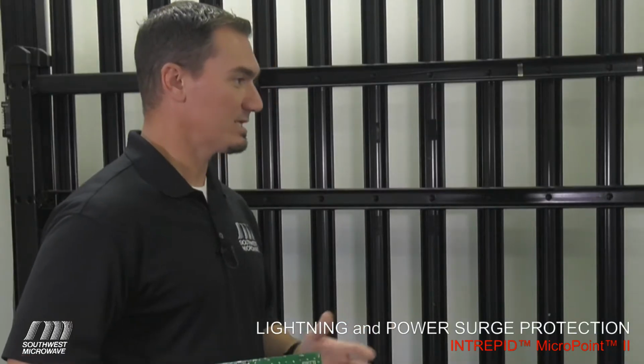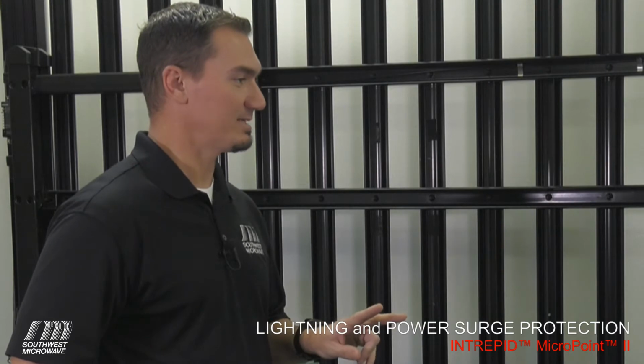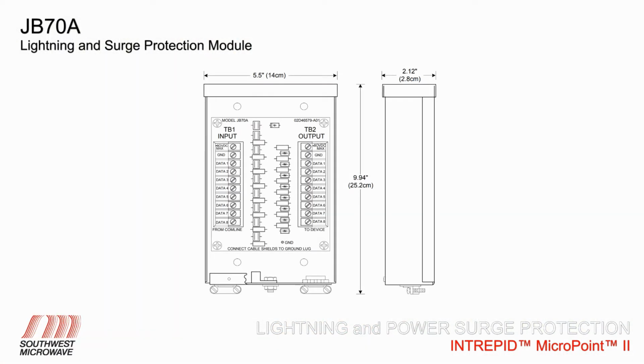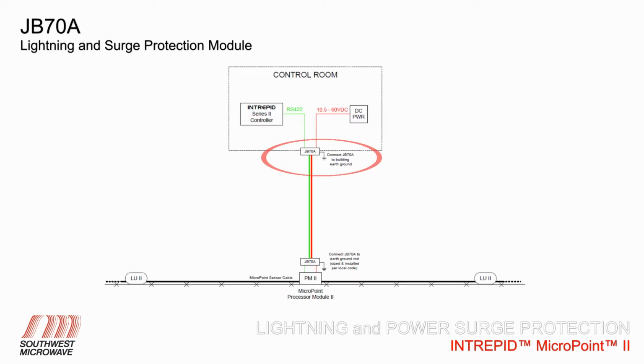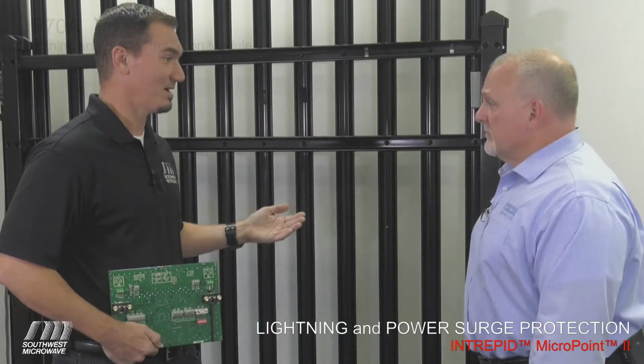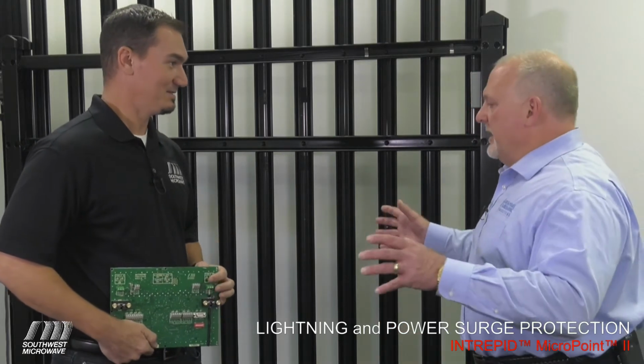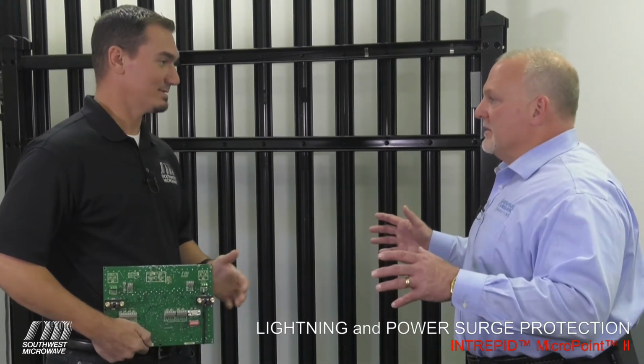The first step we do is apply two surge protection devices, our JB70As. One JB70A is applied at the building, either inside or outside the wall, it doesn't really make a difference. The idea is to protect the electronic components inside the building from induced voltages or surges coming from outside. Then we move out to where the fence is, and we put another JB70A out there. It may be 100 feet, it may be 1,000 feet of wire in the ground and conduit. That could be a potential antenna to induce voltages into the fence system. So you're isolating basically both sides of the system.